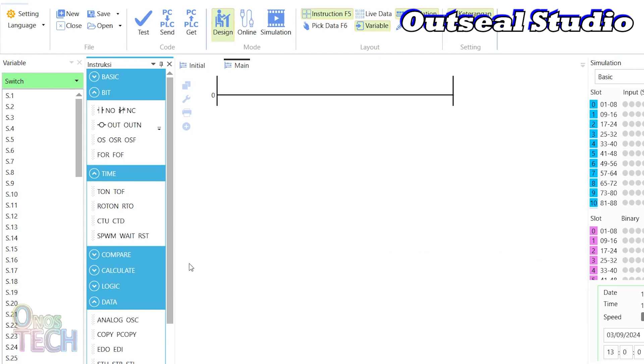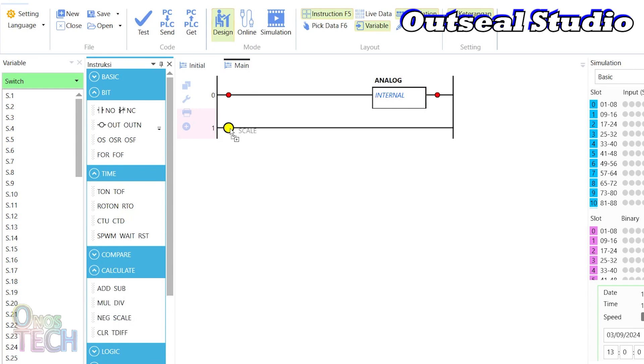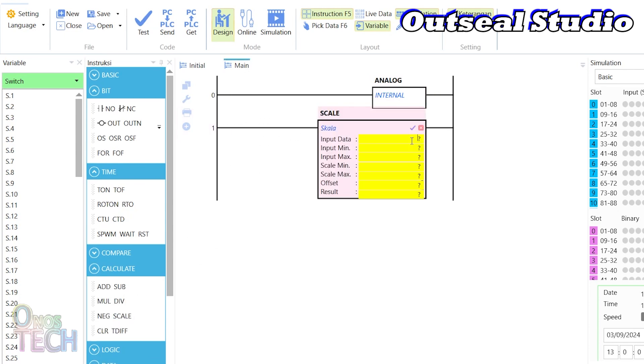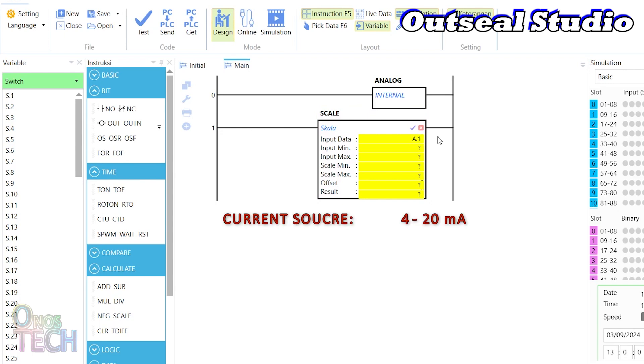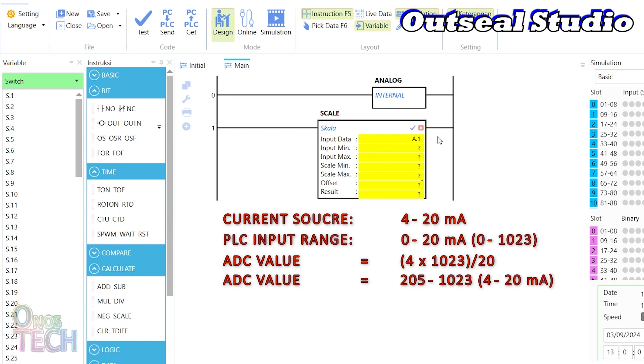Open Outseal Studio and insert an analog instruction into one rung and a scale instruction into another. Set the input data to A.1. Since the current simulator range is 4 to 20 milliamps, and the PLC input measurement range is 0 to 20 milliamps, the ADC value of 0 to 1023 should be scaled to 4 multiplied by 1023, all divided by 20.